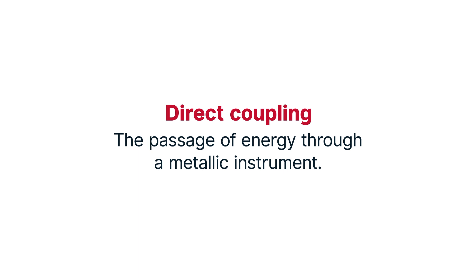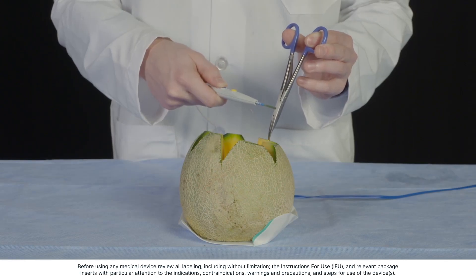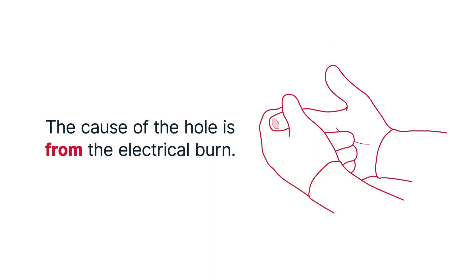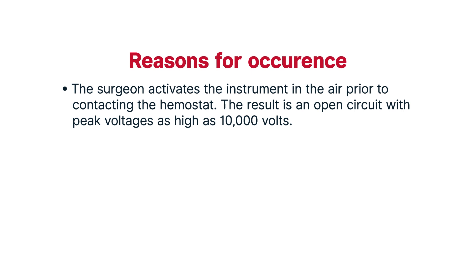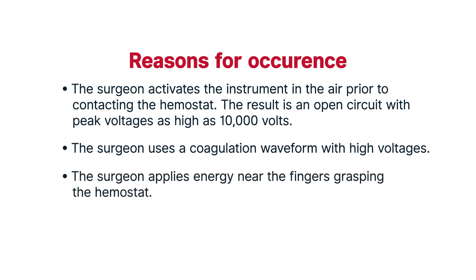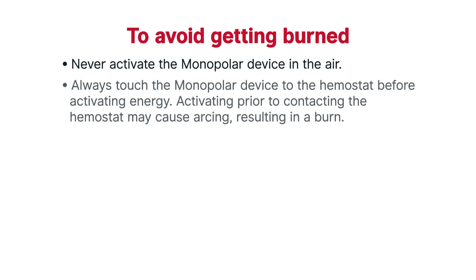Direct Coupling. Direct coupling is the passage of energy through a metallic instrument. Surgeons can be burned when buzzing a hemostat, called intended direct coupling. The injury is often incorrectly attributed to a hole in the surgeon's glove; the actual cause of the hole is from the electrical burn. The burn injury to the surgeon can occur under any one of the following circumstances: the surgeon activates the monopolar instrument in the air prior to contacting the hemostat, resulting in an open circuit with peak voltages as high as 10,000 volts; the surgeon uses a coagulation waveform with high voltages; or the surgeon applies energy near the fingers grasping the hemostat.